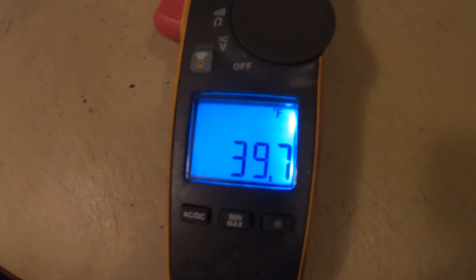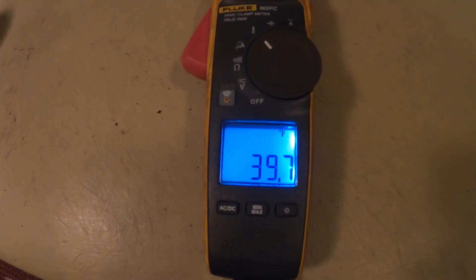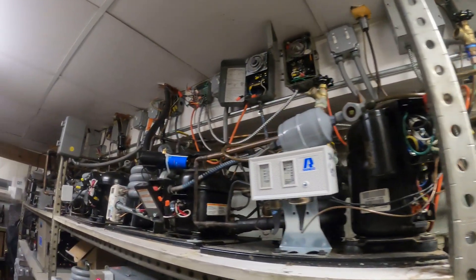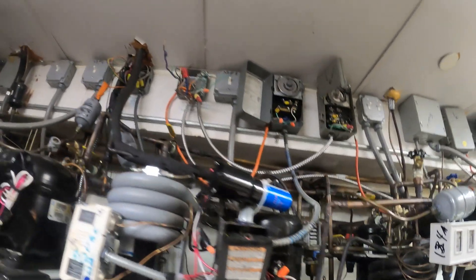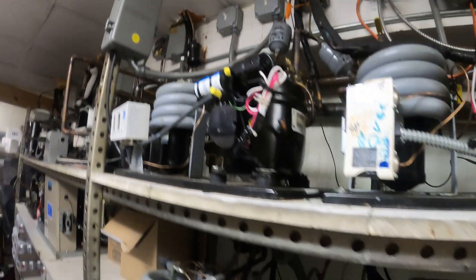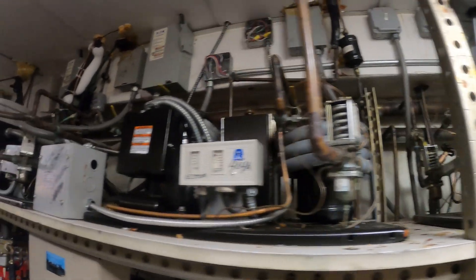Using my multimeter here with the thermometer function — right now we have 39.7 degrees Fahrenheit. You want this to range somewhere between 35 and 40. Let's just watch the temperatures and that's pretty much it — that was the job. Just going to let that box satisfy and that's all. If anyone found this video interesting or helpful, please drop a like, comment, and subscribe as I come out with new videos every week. I'll catch you all next time.